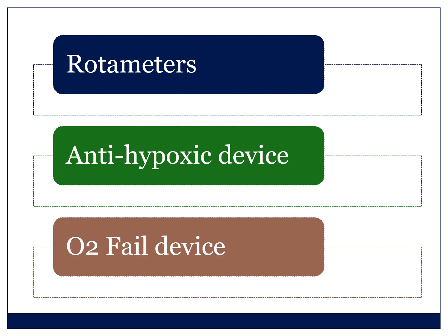And then finally you need to check your oxygen fail device. And basically what you do here is you disconnect the wall oxygen, and there should be an alarm on your machine. There should be an alarm that sounds. Some machines have something called a Ritchie whistle. You then open the oxygen cylinder, and the alarm should go off, and the oxygen bobbin should rise. And then you reattach the oxygen pipeline, repeat the tug test, and close the oxygen cylinder. And that's the proper way to test that all your oxygen sources are working.